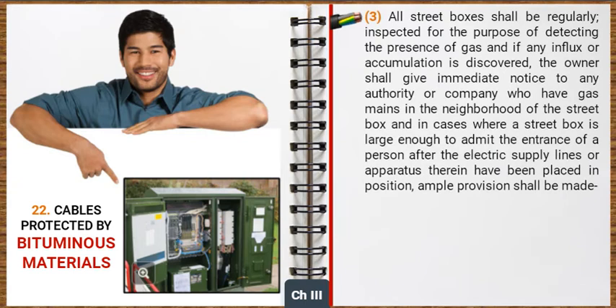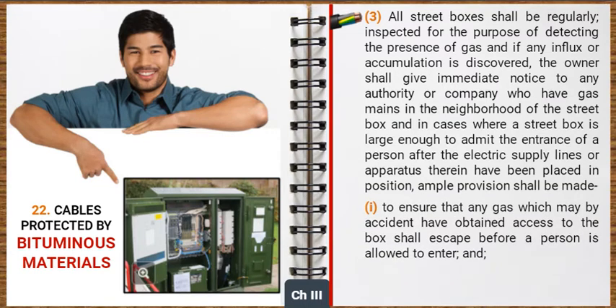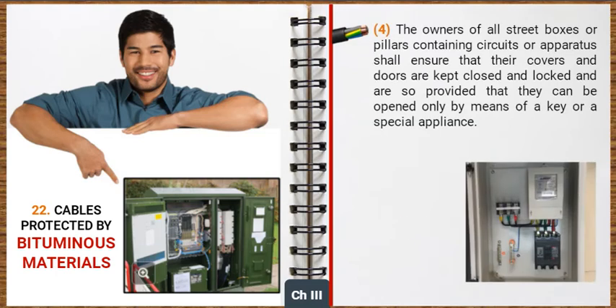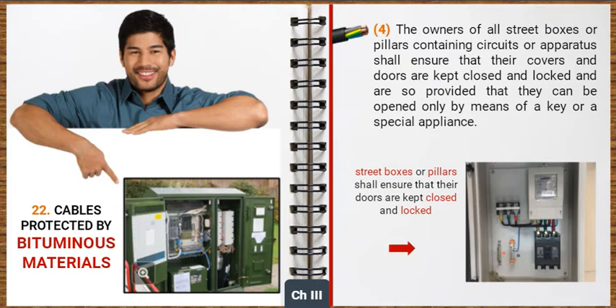Now let's understand the general safety requirements for street boxes. Street boxes shall not contain gas pipes, and precautions shall be taken to prevent as far as reasonably possible any influx of water or gas. Where electric supply lines forming part of different systems pass through the same street box, they shall be readily distinguishable from one another, and all electric supply lines of voltage exceeding 650 volts at or in street boxes shall be adequately supported and protected so as to prevent risk of damage to or danger from adjacent electric supply lines. All street boxes shall be regularly inspected for the presence of gas, and if any influx or accumulation is discovered, the owner shall give immediate notice to any authority or company who have gas mains in the neighbourhood. In cases where a street box is large enough to admit a person, after the electric supply lines or apparatus therein have been placed in position, ample provision shall be made to ensure that any gas which may accidentally have obtained access to the box shall escape before a person is allowed to enter. The owners of all street boxes or pillars containing circuits or apparatus shall ensure that their covers and doors are kept closed and locked, and are so provided that they can be opened only by means of a key or a special appliance.